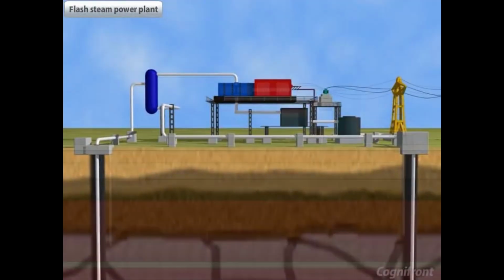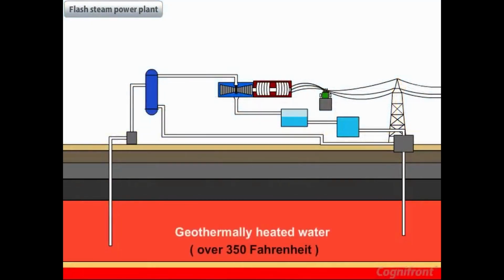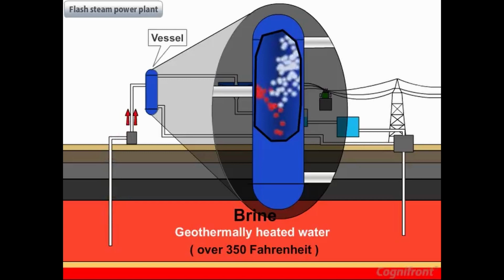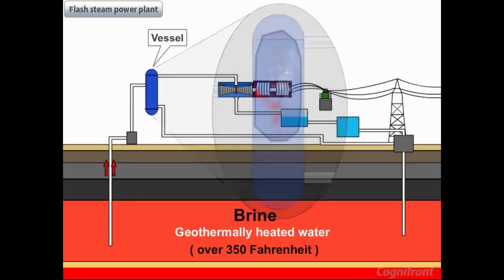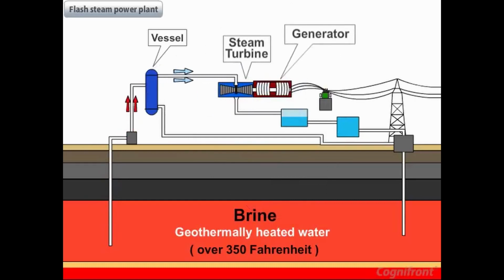The second type of geothermal power plant, which is more common, is the flash steam power plant. The working principle is similar to the dry steam power plant. However, the only difference in this case is that the geothermal heat is in the form of hot water, where the temperature of water is greater than 182 degrees Celsius. The hot water is pumped from the geothermal reservoirs. The change in pressure causes some of the fluid to rapidly transform or flash into steam. The steam then drives the turbine coupled with a generator to produce electricity.